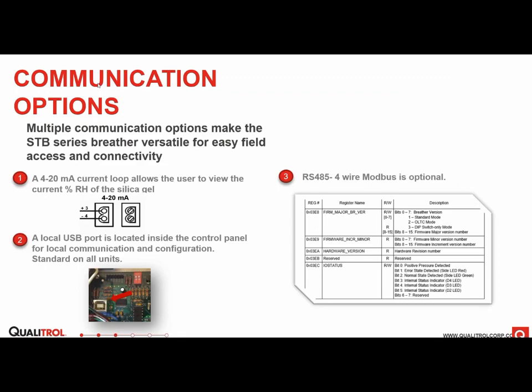So the breather also has some communication options. I touched on the 2 relays. We'll talk more about those in a second, but the breather has an optional 4 to 20 milliamp output, which is the percent RH of the silica. So it's the constant percent RH reading from the breather, and that's over a 4 to 20 milliamp loop.